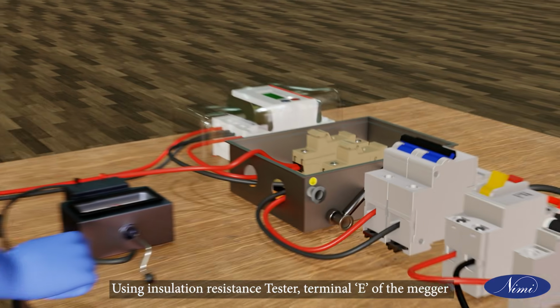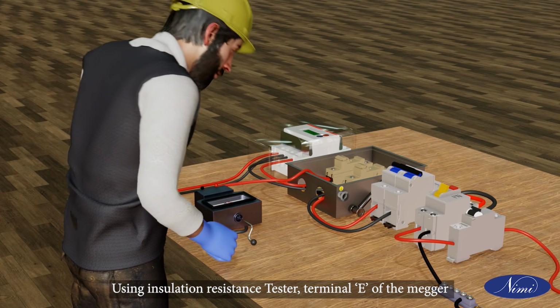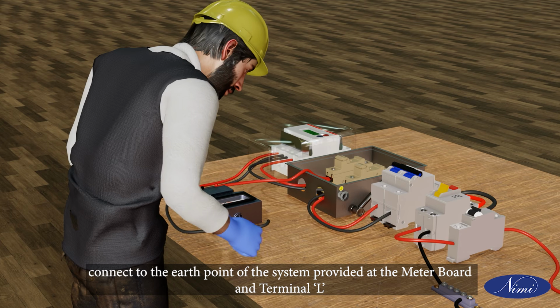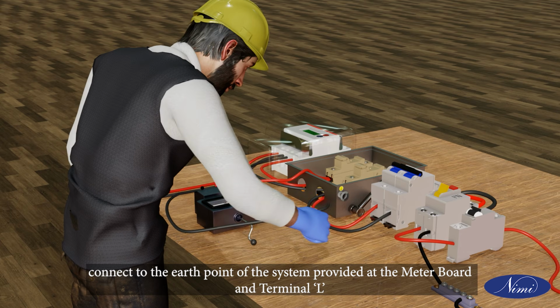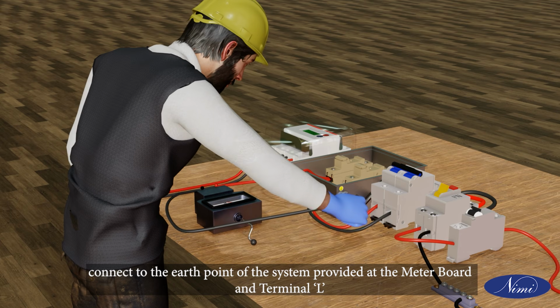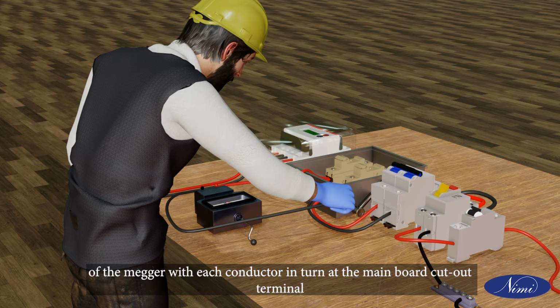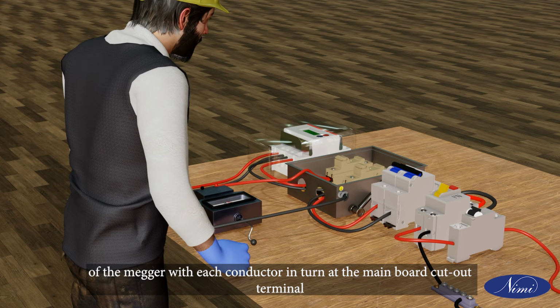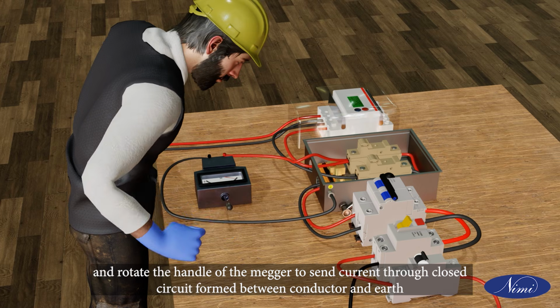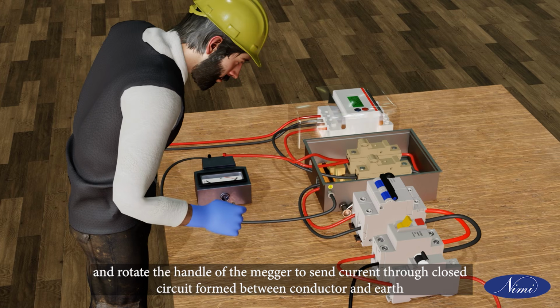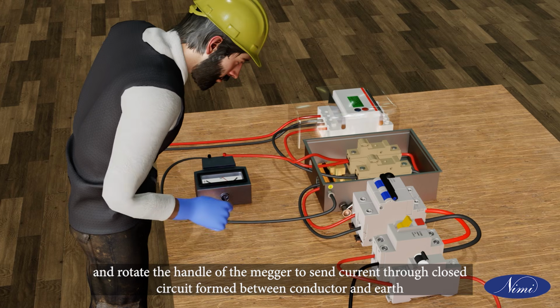Using the insulation resistance tester, connect terminal E of the megger to the earth point of the system provided at the meter board, and terminal L of the megger to each conductor in turn at the main board cutout terminal, and rotate the handle of the megger to send current through the closed circuit formed between conductor and earth.